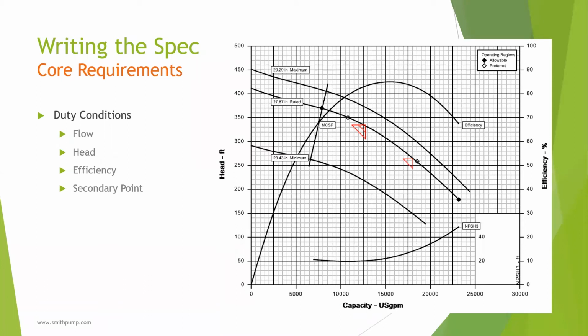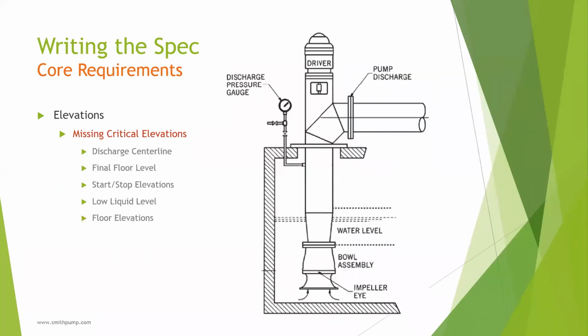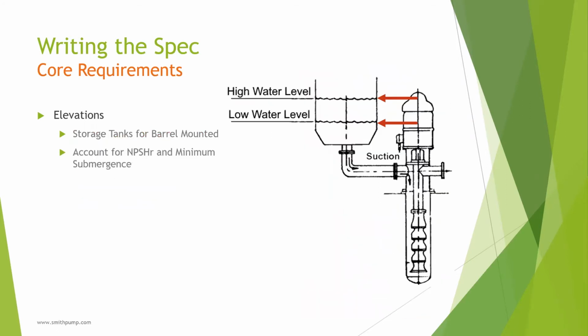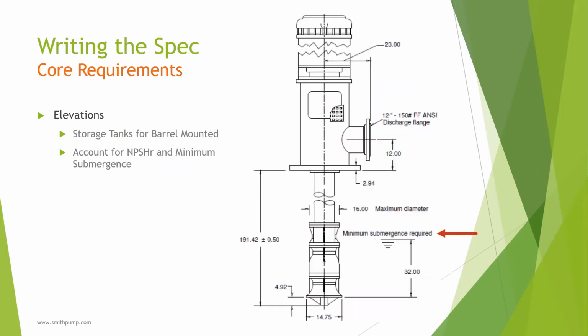So when reading the spec, the first thing the pump suppliers look at are the duty conditions. We want to know the primary rating, the secondary ratings, efficiency, operating range, and so on. Sometimes we find missing elevations in the spec or plans. Key elevation requirements are the discharge center line, the final floor, typical start and stop points, low water level, and floor elevations. If using a barrel mounted pump, define the gravity supply tank's high and low elevations. These levels help us determine pump length to meet NPSH requirements and minimum submergence levels as shown here.